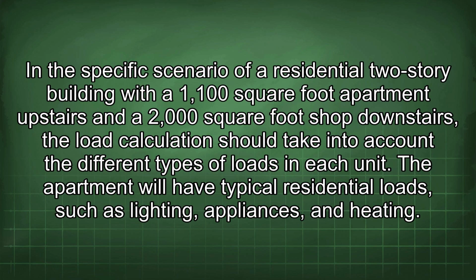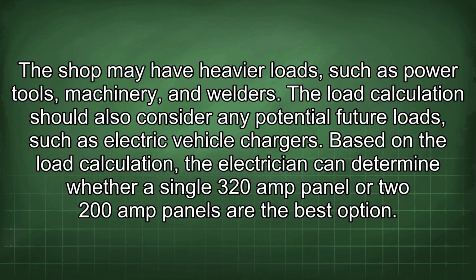In the specific scenario of a residential 2-story building with a 1,100 square foot apartment upstairs and a 2,000 square foot shop downstairs, the load calculation should take into account the different types of loads in each unit. The apartment will have typical residential loads such as lighting, appliances, and heating. The shop may have heavier loads such as power tools, machinery, and welders. The load calculation should also consider any potential future loads such as electric vehicle chargers.